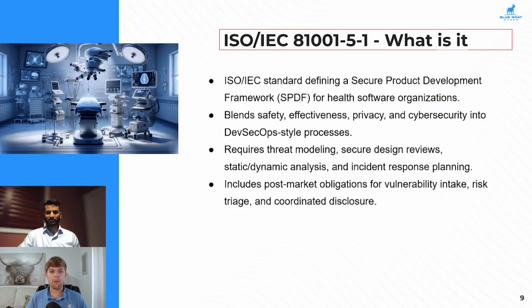It talks about some of the threat modeling requirements, secure design reviews, any static or dynamic analysis, and then incident response planning if there is an event with your product. This also looks into some of those post-market obligations for vulnerability intake, how we're handling triage, and coordinated disclosure. So this goes a little bit beyond the pure development activities, talking about what needs to be done depending on the device class, and tries to branch it out.